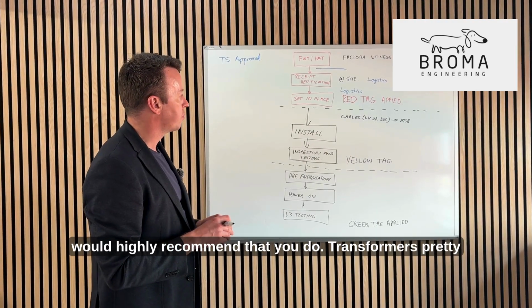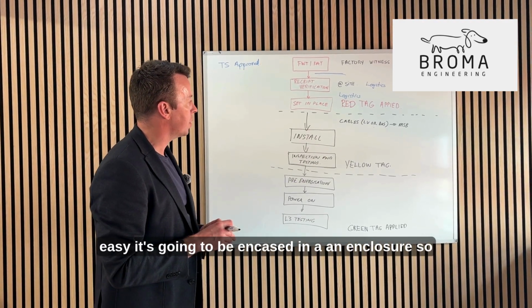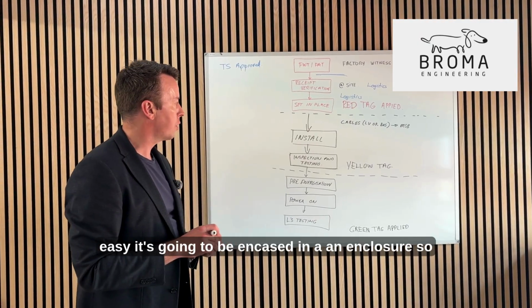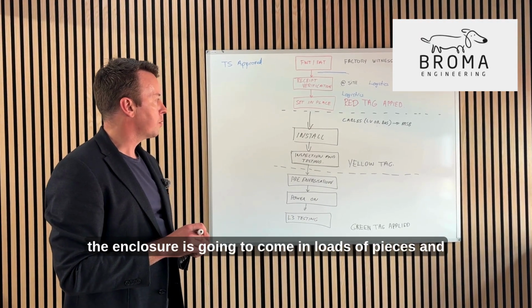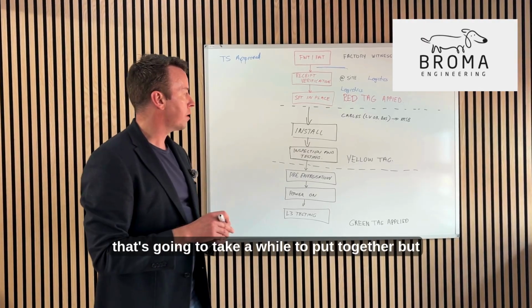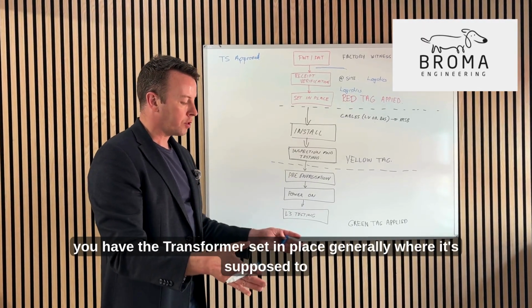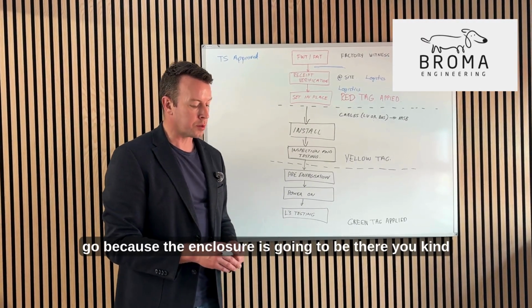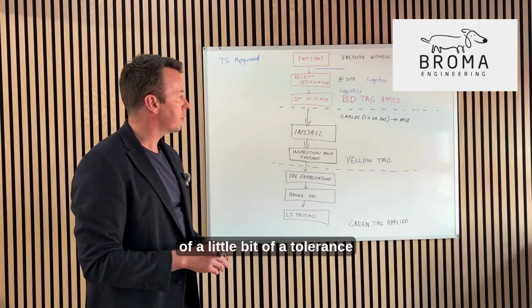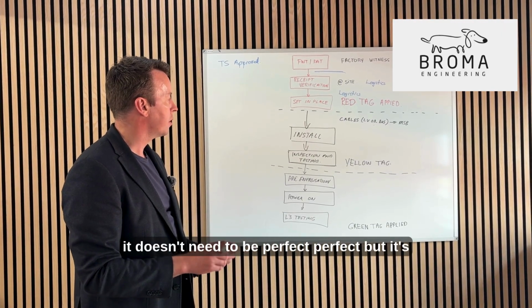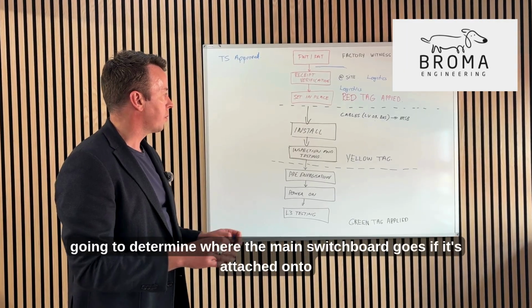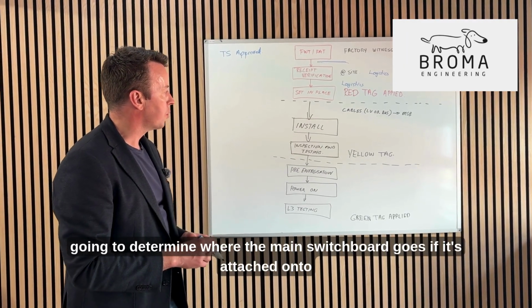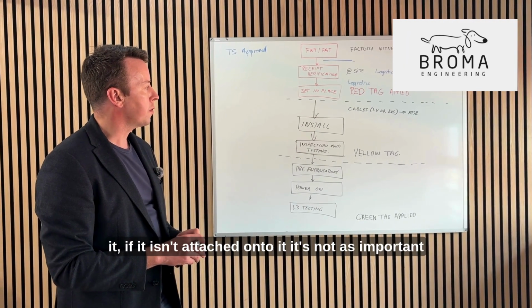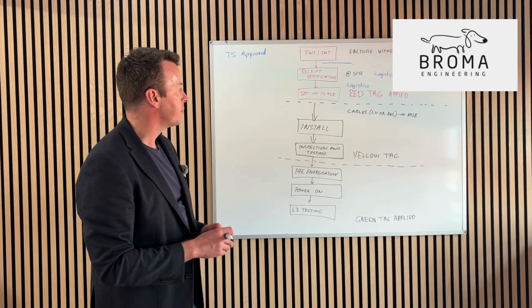Transformers, pretty easy. It's going to be encased in an enclosure, which comes in loads of pieces and takes a while to put together. But you have the transformer set in place, generally where it's supposed to go. Because the enclosure is going to be there, you have a little bit of tolerance. It doesn't need to be perfect, but it's going to determine where the main switchboard goes if it's attached onto it. If it isn't attached, it's not as important.